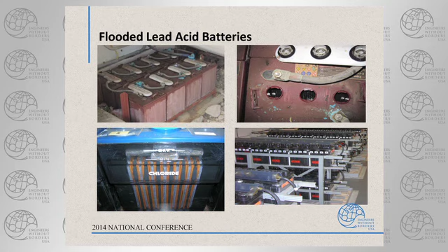Okay, water. Where are you going to get water for these things? Ideally you want distilled water. Everybody remember seeing distilled water in the store at the last developing country you did a project in? No, okay. How about bottled water? Well, it sort of depends. There are minerals in groundwater in certain areas that are bad for the batteries. There are other places where the groundwater would be perfectly fine to put in the batteries. You decide, you've got to find out. If you're in a place with high total dissolved solids, certain minerals, calciums, other things, not good. So you've got to find out.